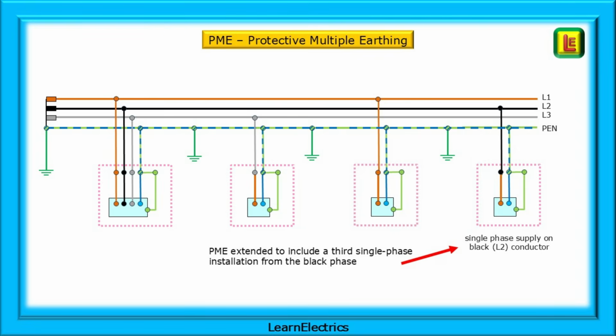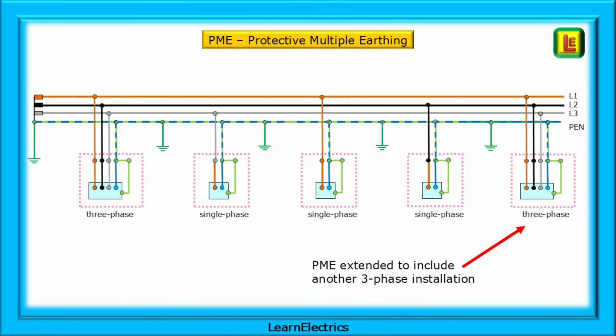As three-phase will run along the street outside your house, it is relatively easy but expensive to have the DNO upgrade a property from single-phase to three-phase if circumstances changed and it was required. And on this drawing, imagine a new property is built, a small commercial unit for example, and the DNO is asked to supply three-phase to the building. This is not a problem with a PME system, subject to existing and anticipated loading criteria.